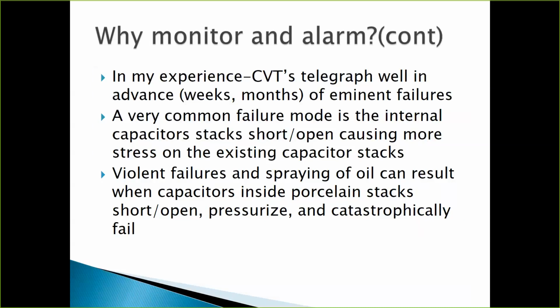What they do is a typical common failure mode for these capacitive voltage transformers is the capacitors in that stack will either short or go open. So think about this. If you have a fixed amount of capacitors and you lose one, that same voltage is expressed across less capacitors, which tend to cause more stress on the existing capacitors and they start to fail. So they don't typically fail all at once. It's a gradual thing. So this is something we can exploit.